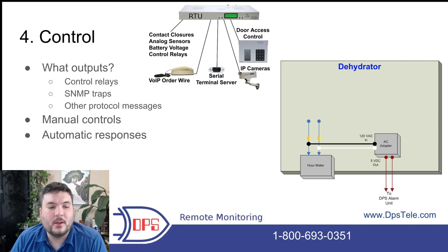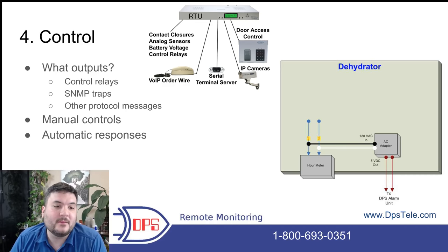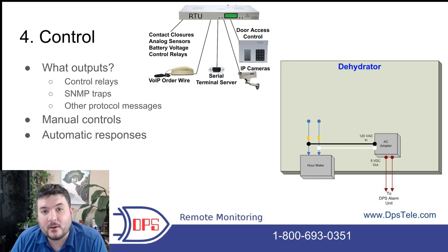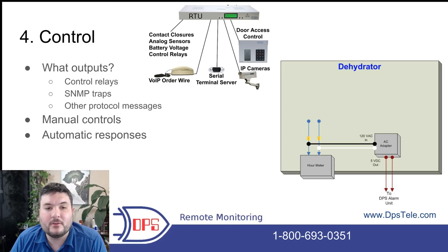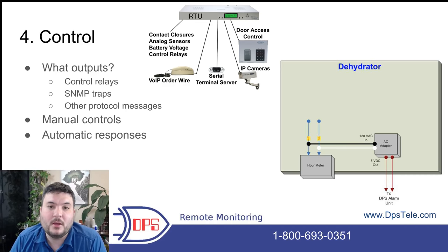The last part of SCADA is control. Key questions: what outputs do you have? Looking at the RTU diagram, you can see control relays on the left side — you can latch contact closures, and equipment with discrete inputs can pick that up to fire up a generator or turn on HVAC units. A good rule of thumb: if it has a button or a switch, you can wire it into a control relay and simulate that flip or button press. You can also send SNMP traps to devices that accept them, telling a server to shut down or executing various actions. If you have DNP3 or Modbus, you can send a protocol message as long as your RTU is compatible.